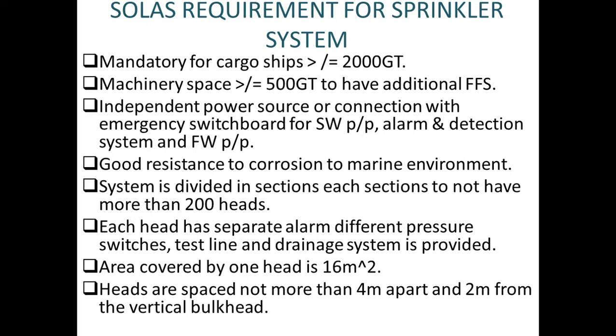Now, independent power source, always keep this in mind, because any emergency system has to have an independent power source, or a connection with the emergency switchboard. Either of the two can be done. If we don't have an emergency power source, then we can have a connection with the emergency switchboard for the seawater pump. We'll discuss it, because basically in the sprinkler system we have fresh water, and we also have a seawater connection, for the alarm and detection system, as well as for the freshwater pump.